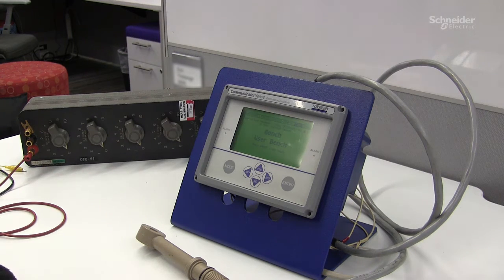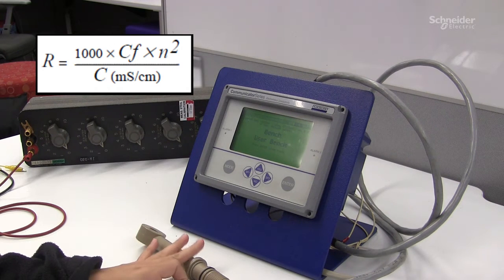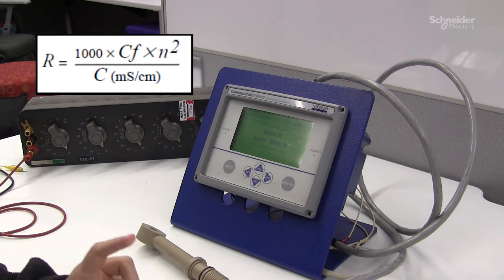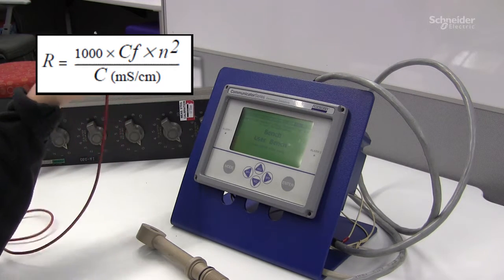It says that the resistivity that you require to use will be equals to a thousand times the cell factor of your specific sensor type, times the number of loops of the wire coming out of the decade box through the sensor board squared, and then divided by the conductivity required.